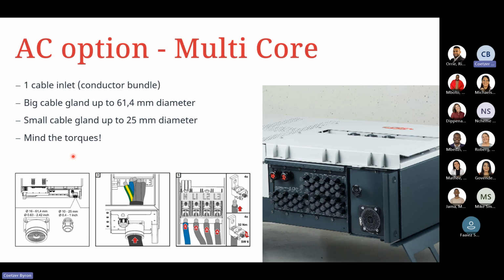We can also do multi-core. This allows for one cable inlet, a conductor bundle. Big cable glands allow for up to 61.4 millimeters in diameter, and small cable glands up to 25 millimeters coming in. Again, we always say to mind the torques. Depending on which cable you're using, aluminium or copper, keep in mind the torque ratings when you are fixing the AC cable.